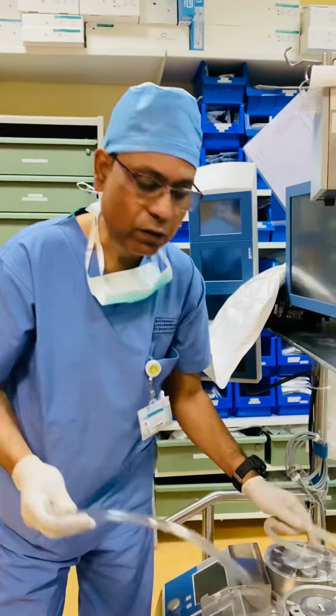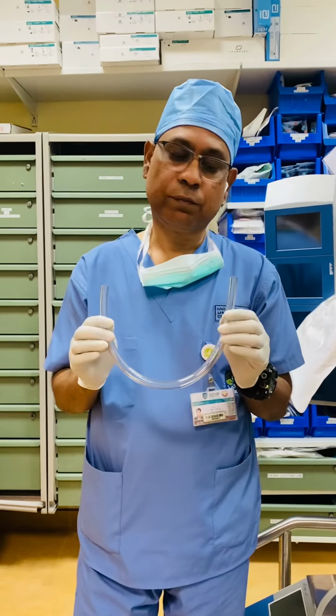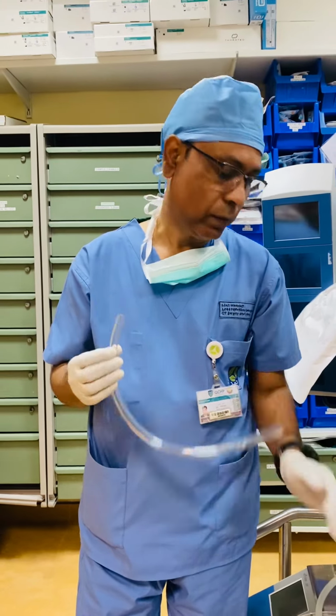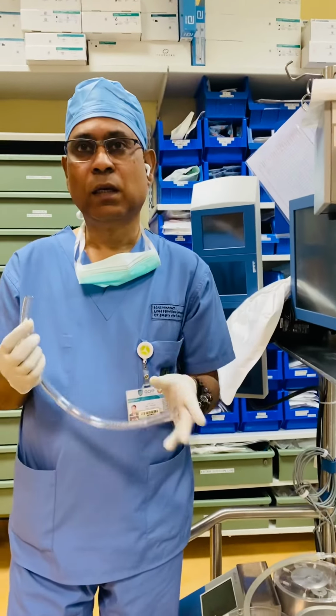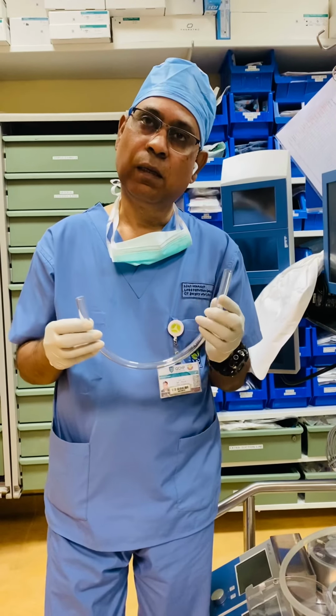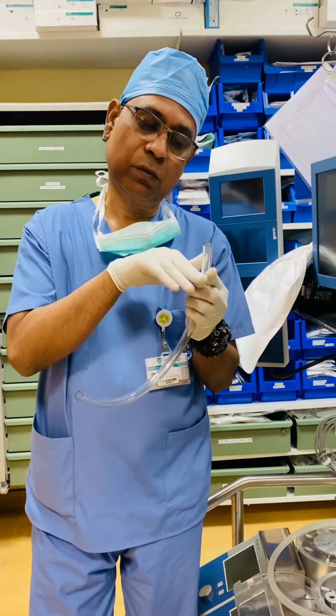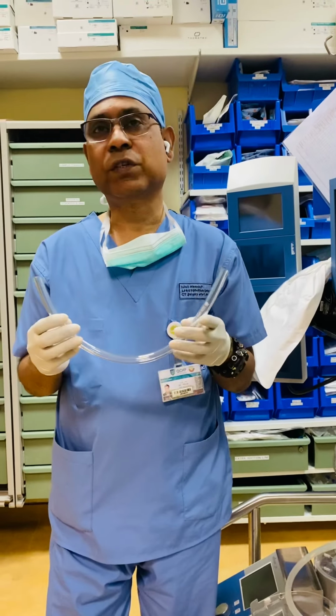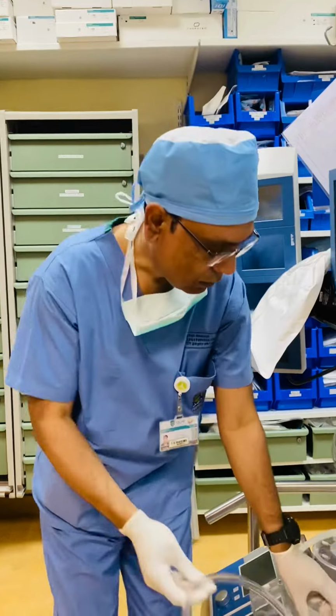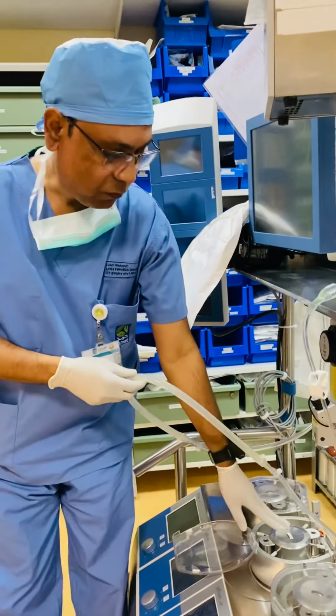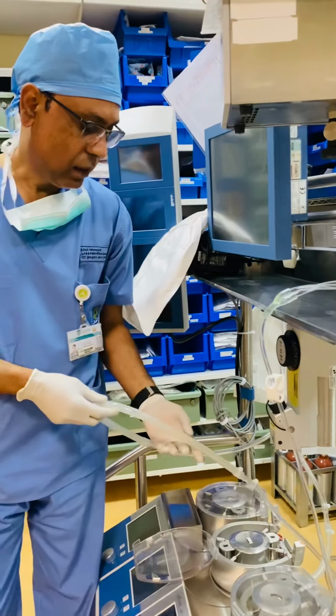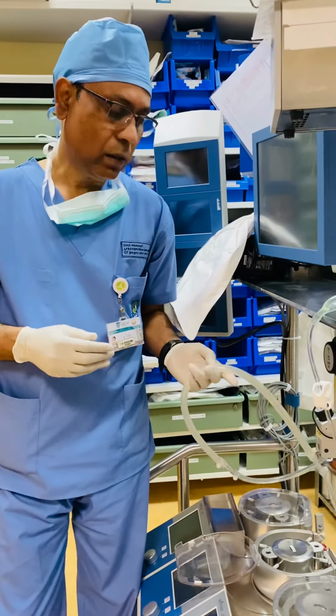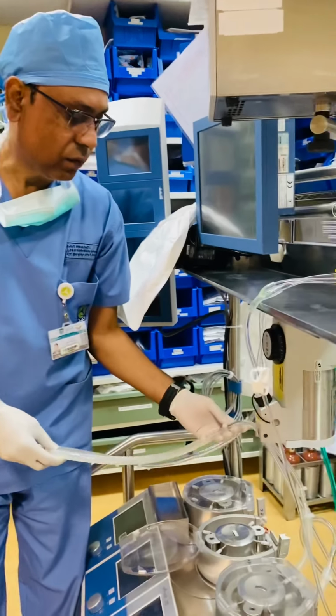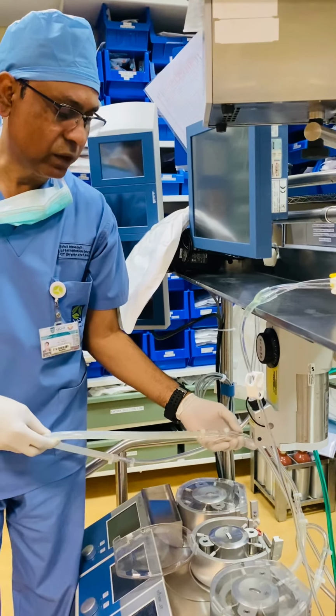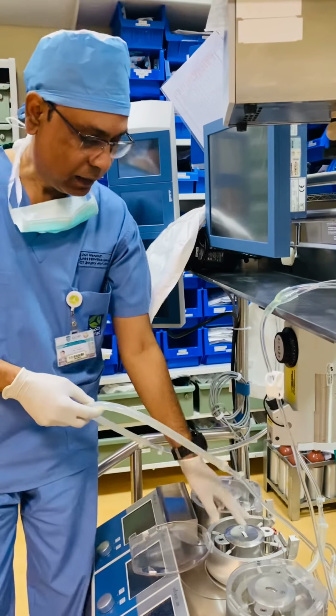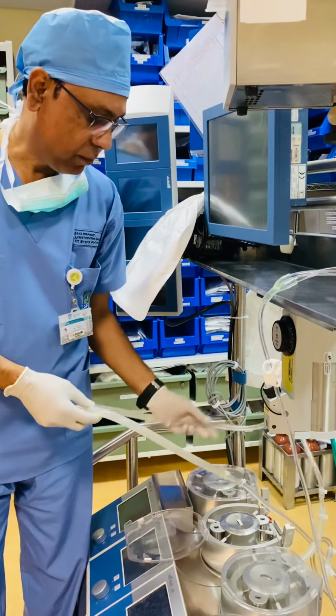What will happen if we use a PVC tube in the roller head? As I mentioned, it will break your cells. By the roller pressing hard onto the tube, there is a chance of destruction of the cells. The recommendation, especially for the pump and for the vent, like the pump suckers, is to use silicone of a bigger size, converting to a lower size. Normally we have the 1/4 which takes the suction from the body, and in a pump head we have the 3/8 and return back with the 1/4.